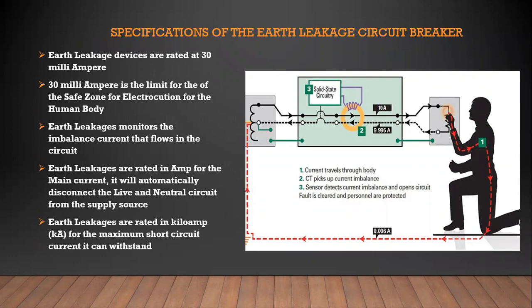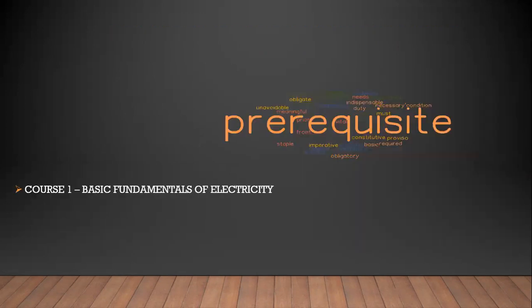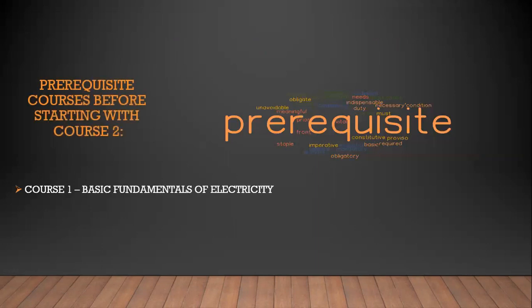What is touch voltage? Often, and this comes back to bonding, the client will tell you, when I touch the shower taps or the taps in the kitchen, I get a little tingling in my hands. That is leakage current. So actually, there is not correct bonding done, and there's a leakage current inside the element. And this will explain to you what leakage current is, how the earth leakage picks it up, and what the maximum allowable leakage current is to flow through any circuit to make it safe for human beings. And I also address the leakage currents which the human body can actually take before it gets electrocuted.